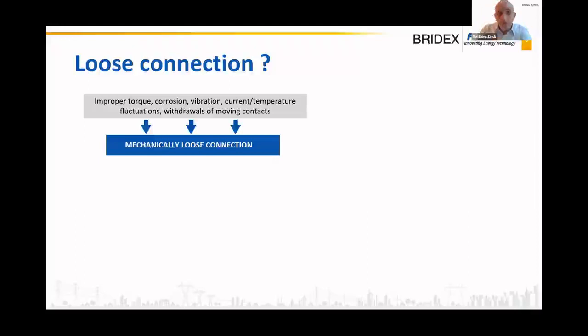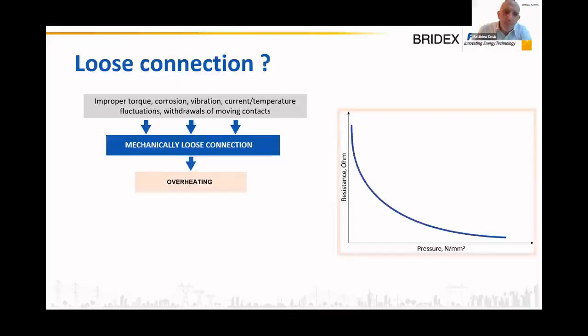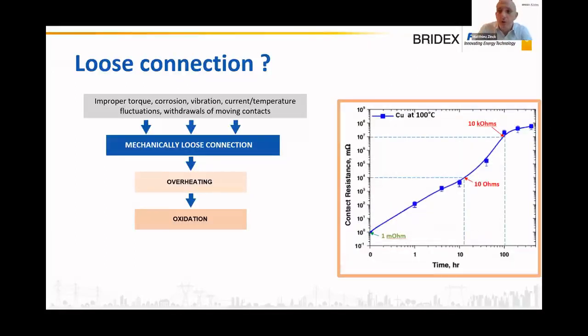So basically, when you start from a situation where you have a mechanically loose connection, you will have overheating because basically the less the pressure, the higher the resistance. So if you have a higher resistance at the contact point, it will basically work like a heater. And this will lead to oxidation. And so the phenomenon of oxidation is described here in the curve.